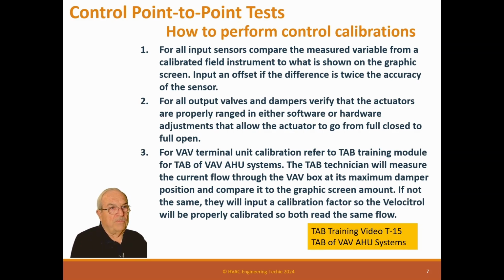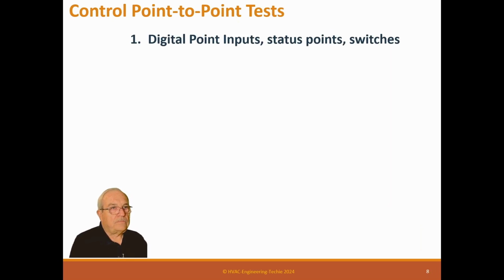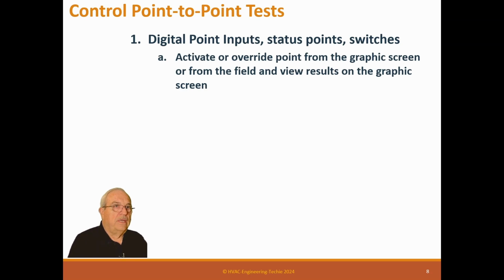So I said, also back up to number 2, when you're ranging an actuator, it's really important everything goes full closed. It's not actually required they go 100% open. That's not a problem, but 100% closed is really important. So what you do is you adjust the linkage on the valve or the damper to make sure they go closed. Digital point inputs, status point switches: activate or override the point from the graphic screen or from the field and view results on the graphic screen.